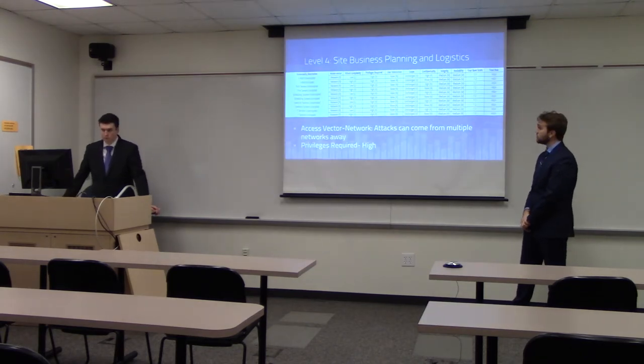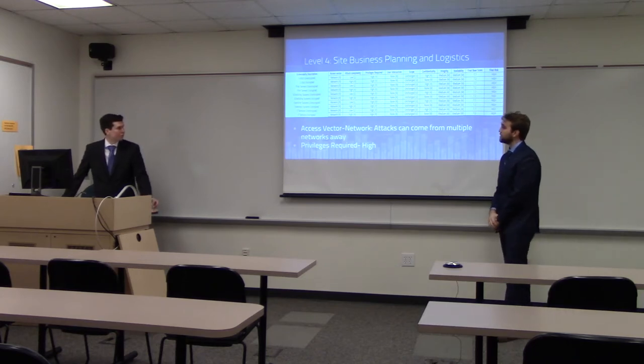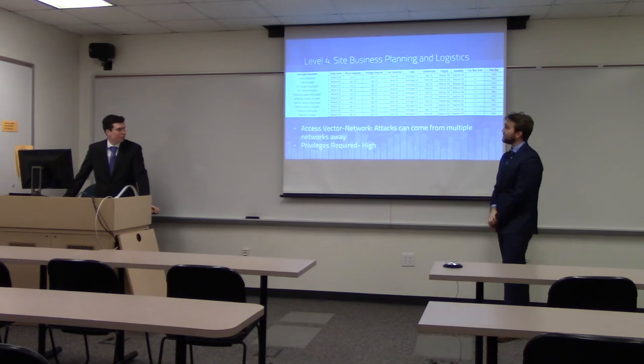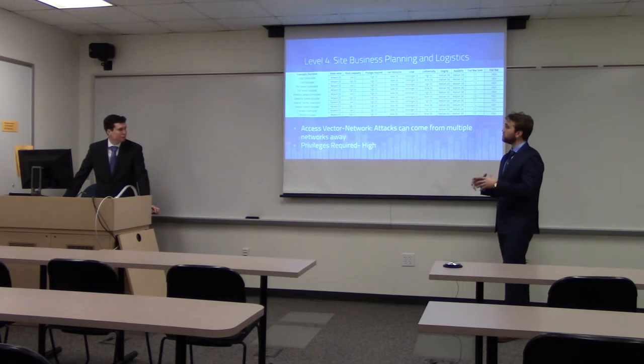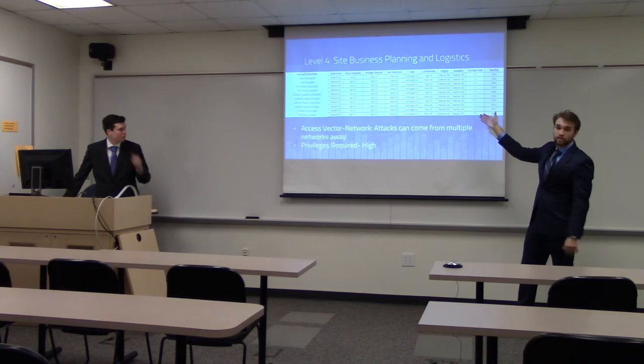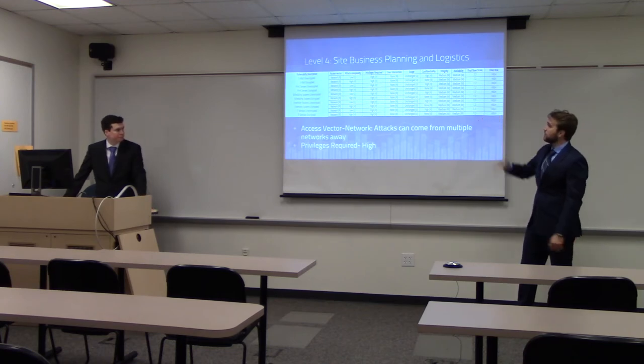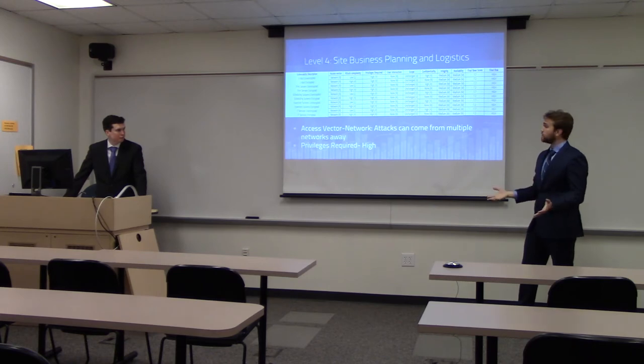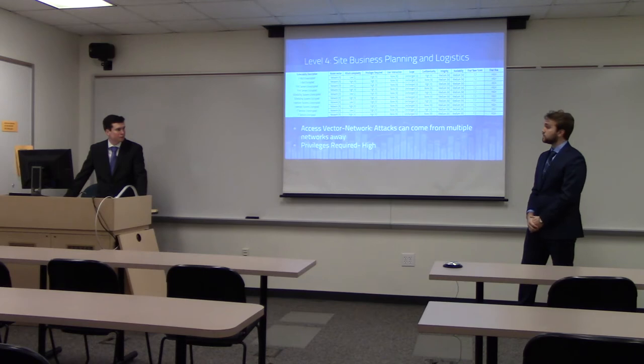This is level four, the site business planning and logistics level. The access vector is now network, meaning attacks can come from multiple network hops away without being within the facility. Privileges required are high even for unencrypted systems at this level, because critical infrastructure facilities consider this data naturally more valuable and require more privileges to access it.